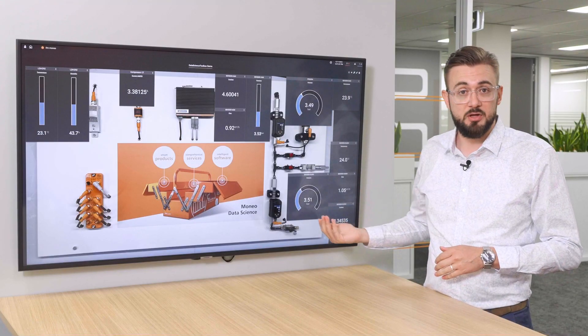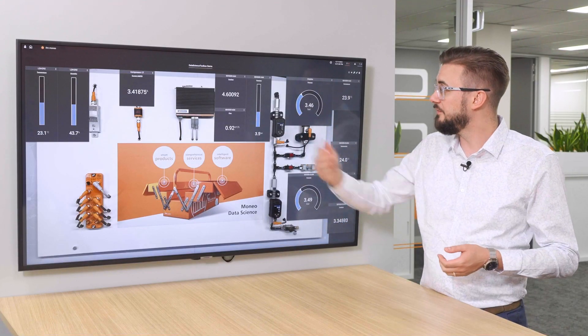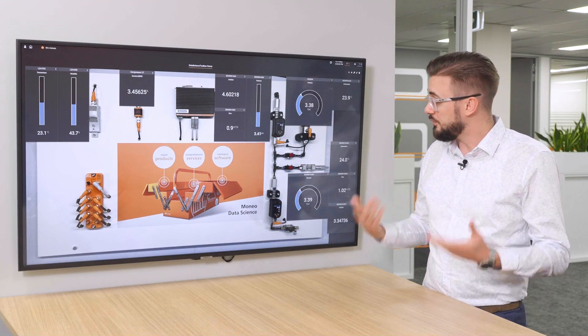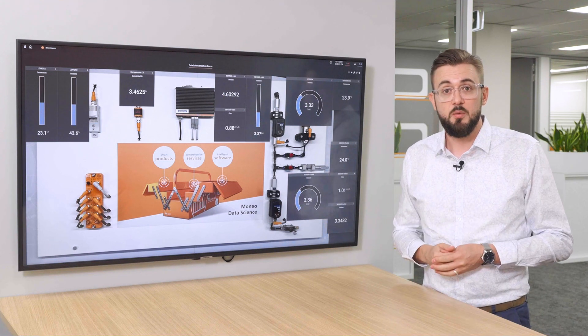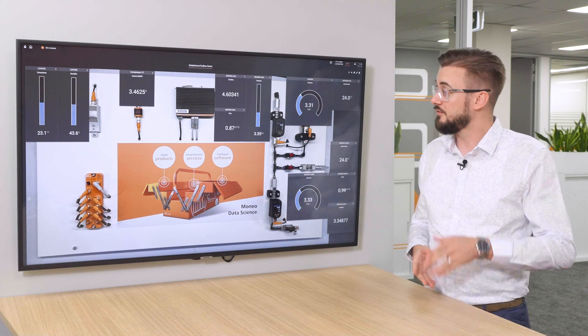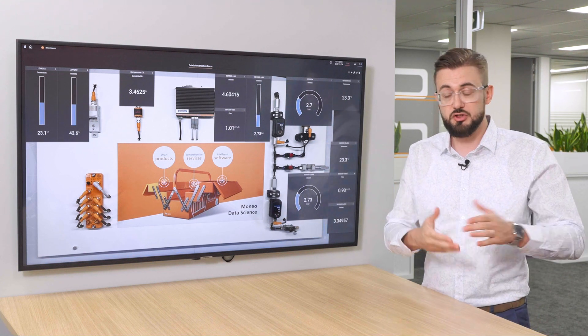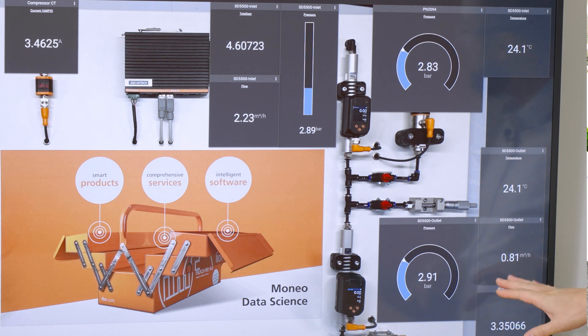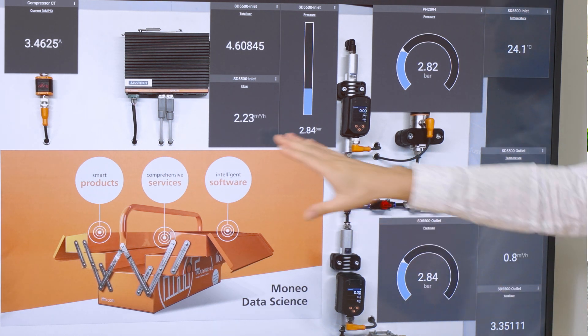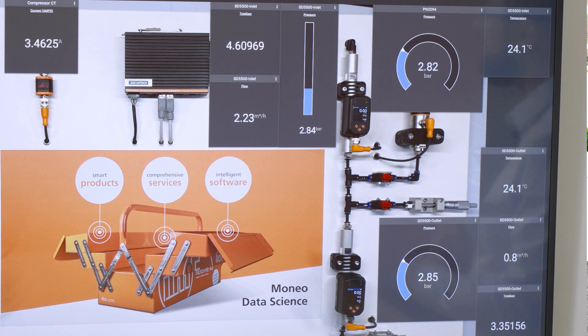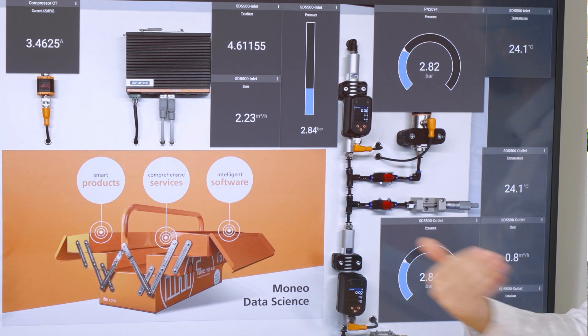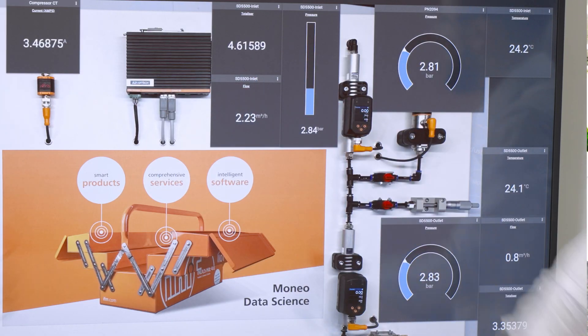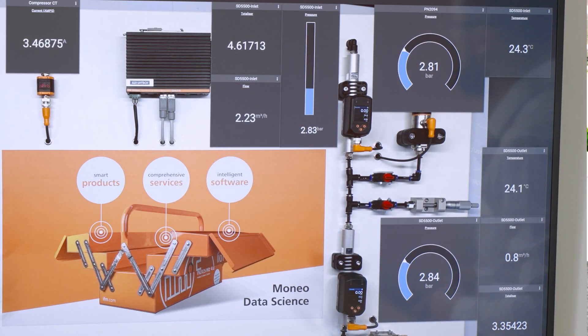In a typical running environment the plant will run perfectly — the compressor will supply its load and the plant will need that load. In scenario one, we introduce a leak into the system. You can see the plant is consuming exactly the same amount, but the compressor is working harder because it's trying to feed the system while there's a leak. In return, the amps are going up as well, meaning we are consuming a lot more energy.